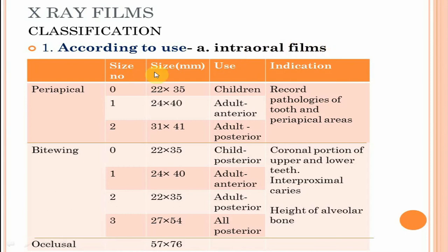There are three types of intraoral films: periapical films, bite-wing films, and occlusal films. Based on size, periapical films have three types: Size 0 is 22 x 35 mm used in children, Size 1 is 24 x 40 mm for adult anterior region, Size 2 is 31 x 41 mm for adult posterior region. Bite-wing radiographs have four sizes: Size 0 is 22 x 35 mm for child posterior, Size 1 is 24 x 40 mm for adult anterior, Size 2 is 22 x 35 mm for adult posterior, Size 3 is 27 x 54 mm for all posterior. The occlusal radiograph comes in size 57 x 76 mm.